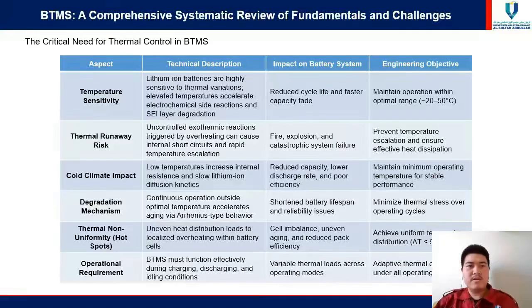Okay, next is the critical need for thermal control in BTMS. The technical need is critical because lithium-ion batteries are highly sensitive. High temperatures accelerate capacity fade, while uncontrolled exothermic reactions can lead to thermal runaway, resulting in fire or explosion. We also cannot ignore the impact of cold climates, which increase internal resistance and slow down lithium-ion diffusion, leading to reduced capacity. Our engineering objective is to maintain an optimal range of 20 to 50 degrees Celsius to minimize thermal stress over the battery's lifespan.